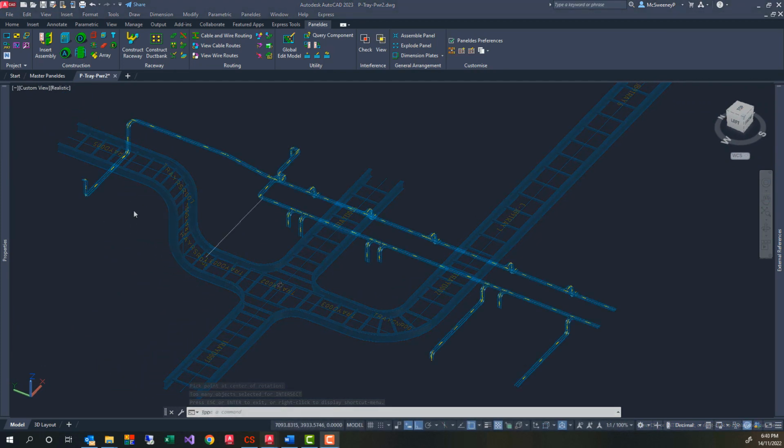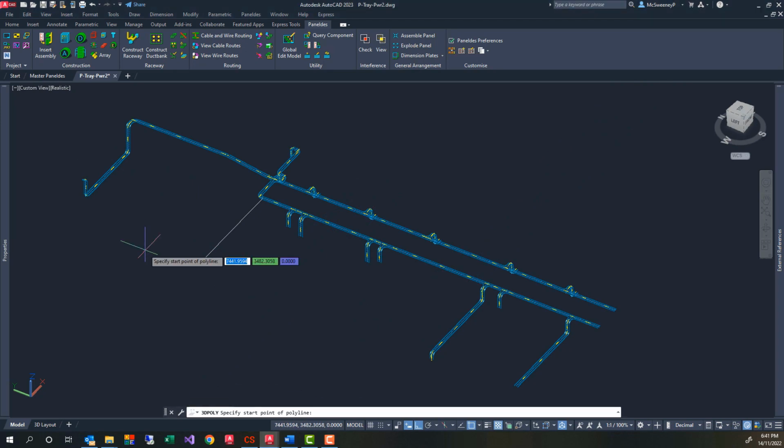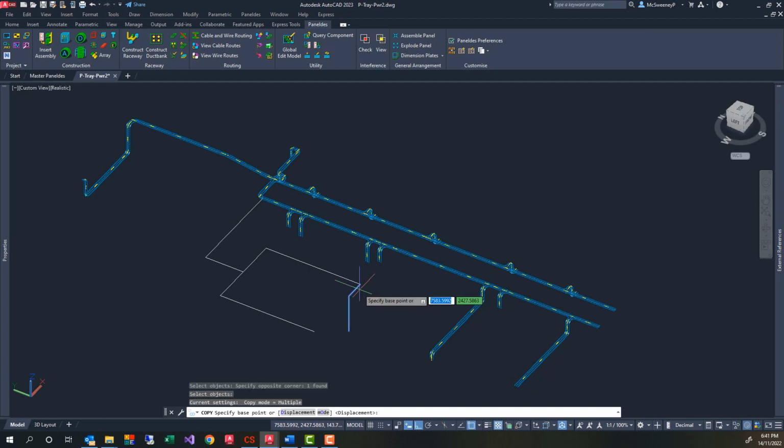This is the polyline trace method. Polytrace brings extreme automation to the design of Raceway. You draw the Raceway paths and junctions with a 3D polyline, and we create a realistic 3D model of the Raceway from these polylines. You can use any of the out-of-the-box CAD functions to create the polylines. We provide a small tolerance for junctions on the polyline network. If Paneldes sees a junction within that tolerance, then it will use a fitting to join the trays.